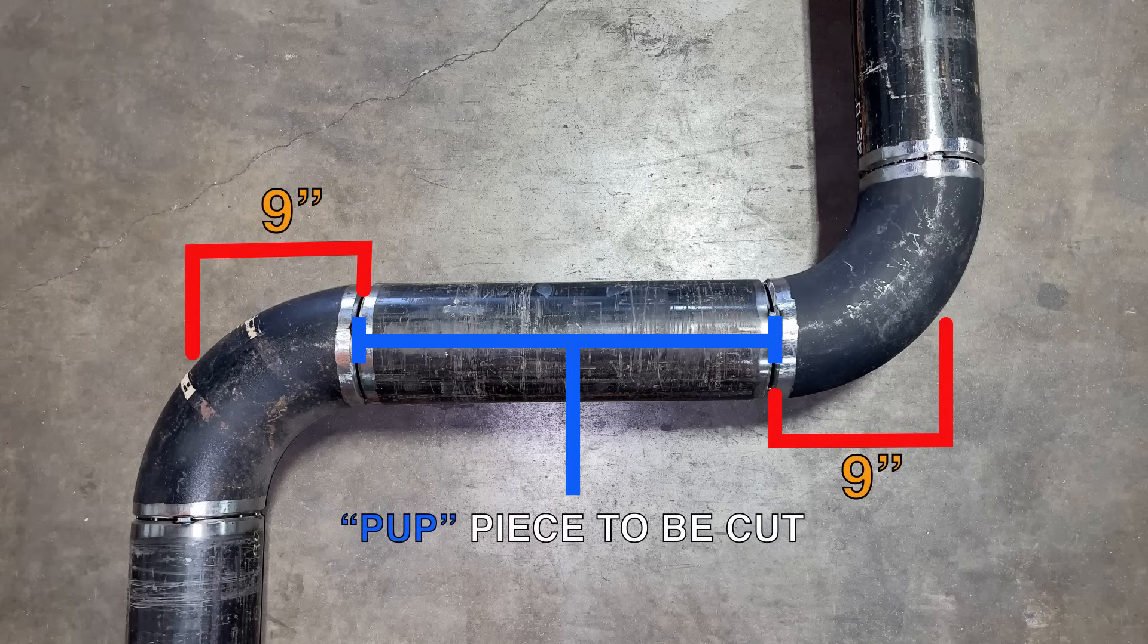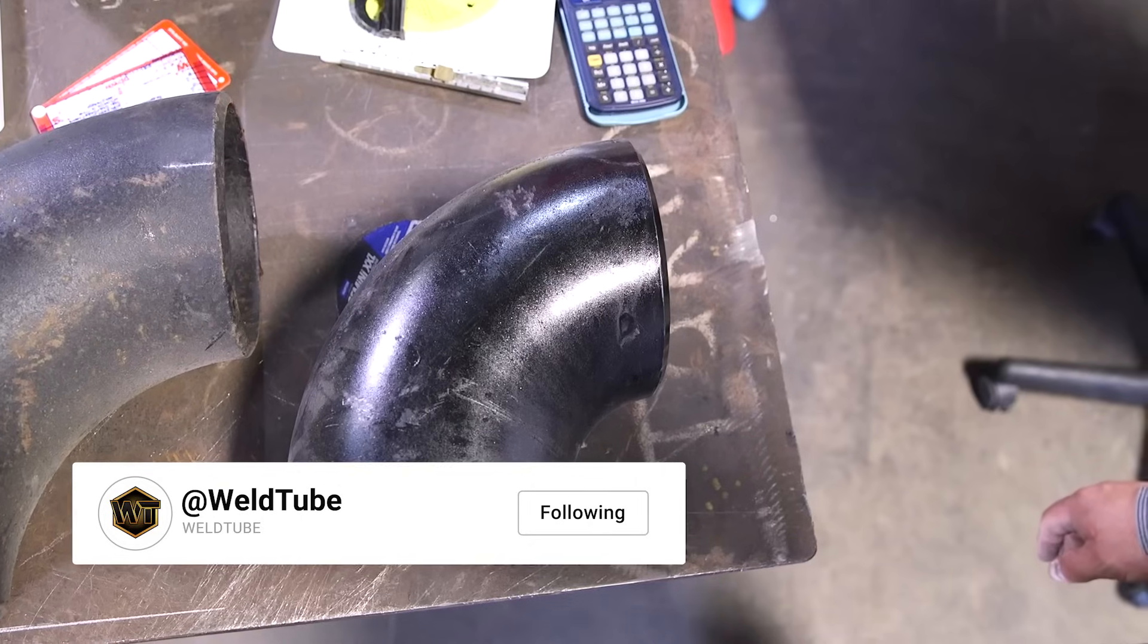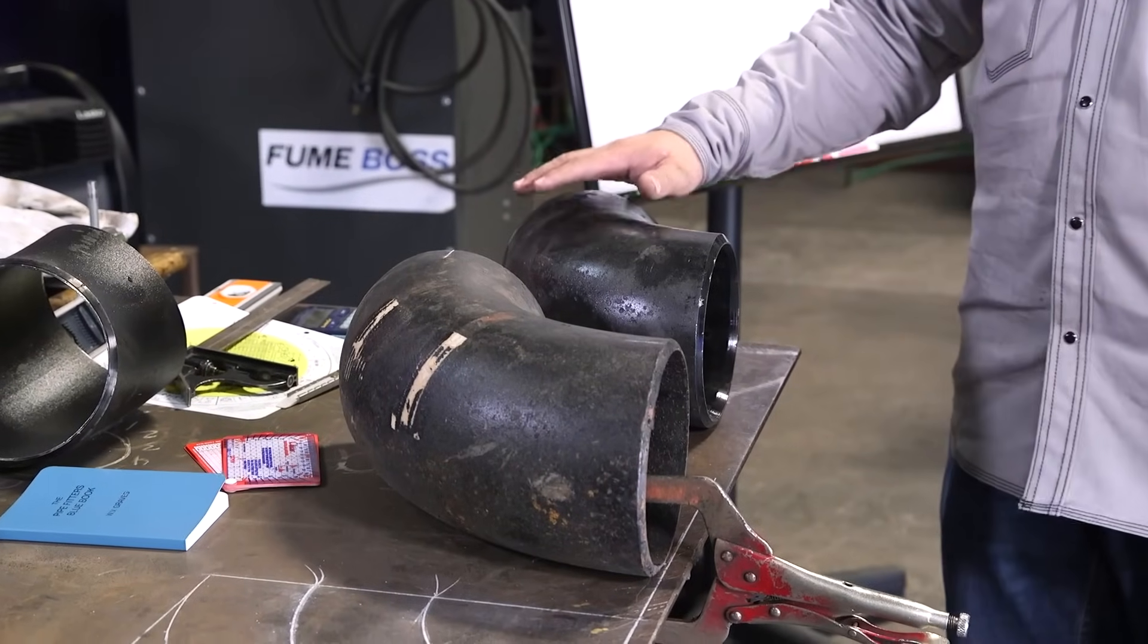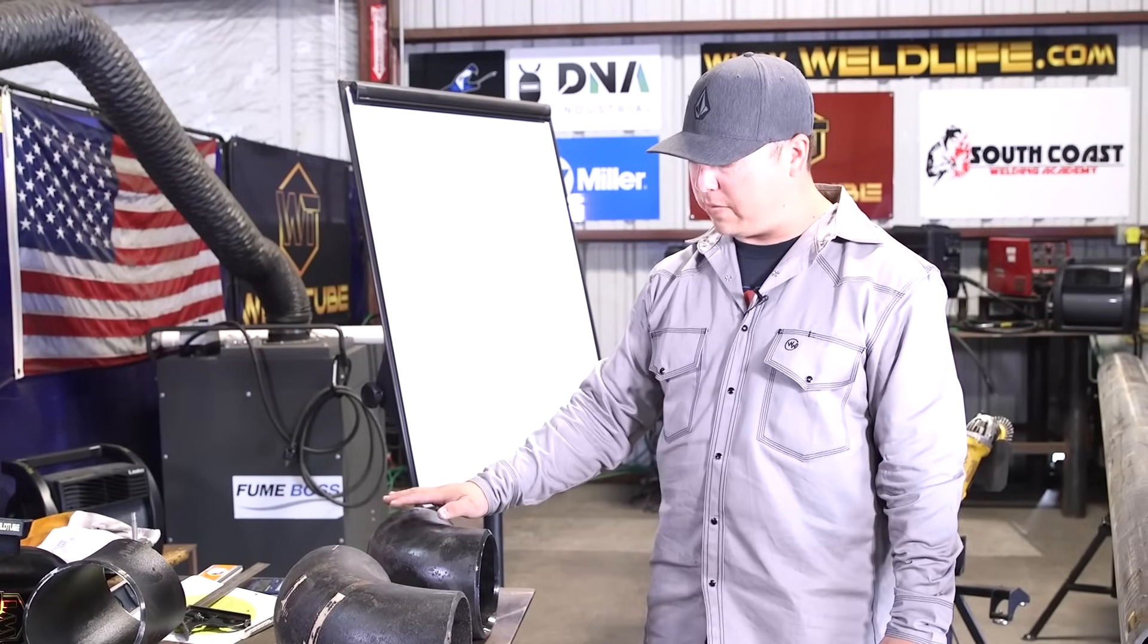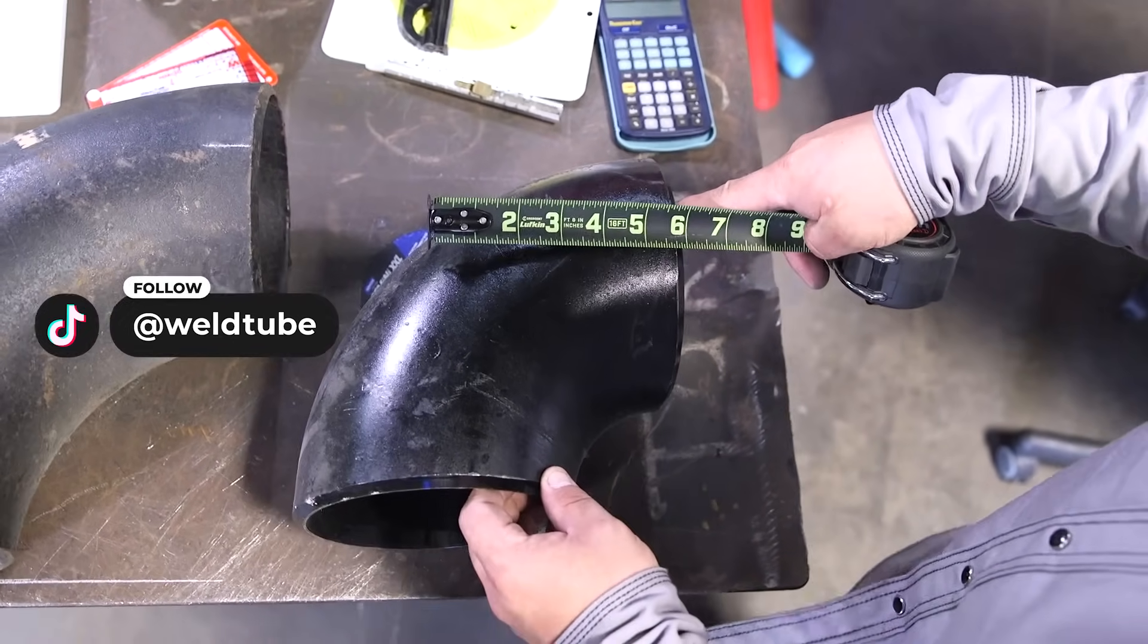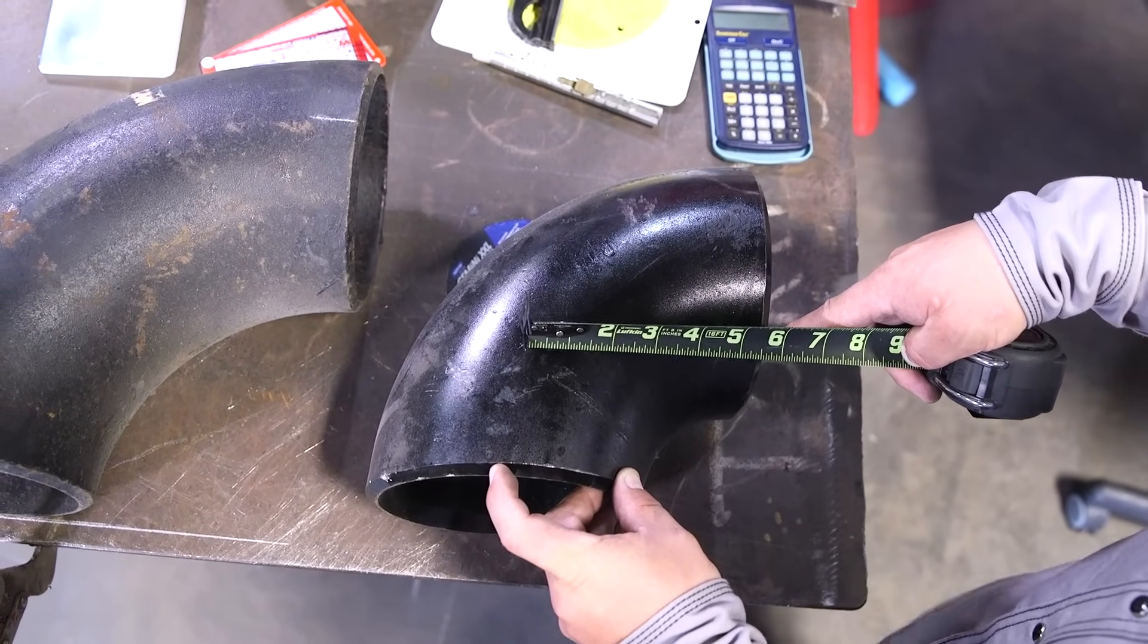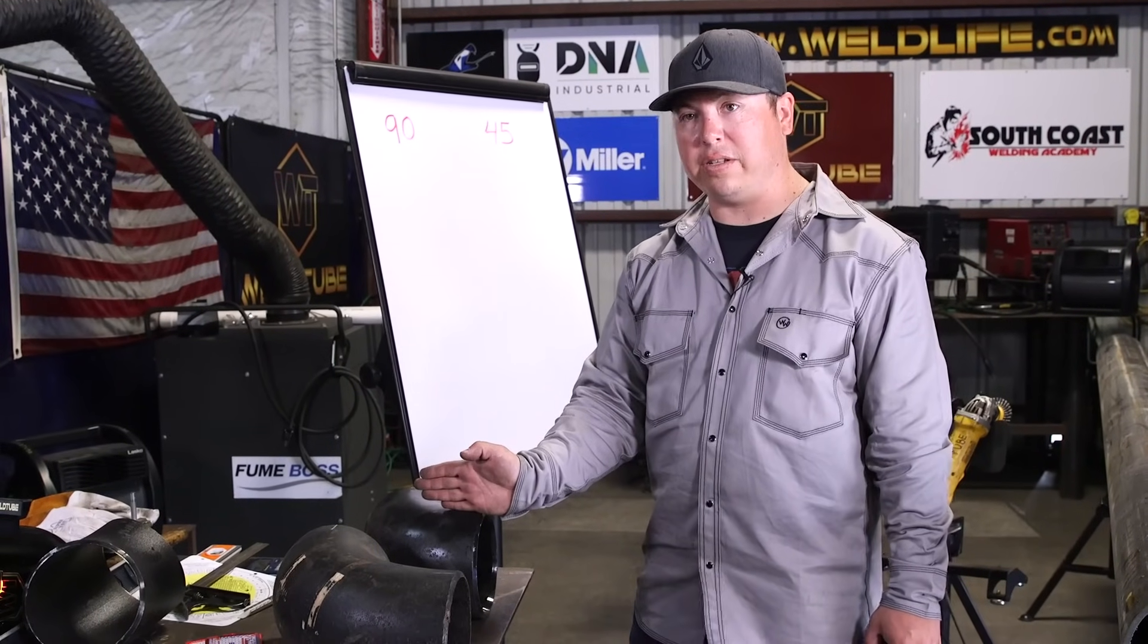So you may have heard me say the term long radius 90. A lot of you may have not known what that is. As you can see the difference here, I have a long radius 90 and a short radius 90. The short radius 90 has a much tighter turn and the takeoff is very different than a long radius 90. On the short radius 90, you're only going to remove one nominal pipe size for your takeoff. So in this particular case, we have a 6 inch short radius 90. Our takeoff from end to center of 90 will be 6 inches.